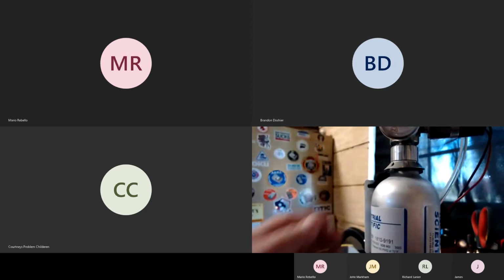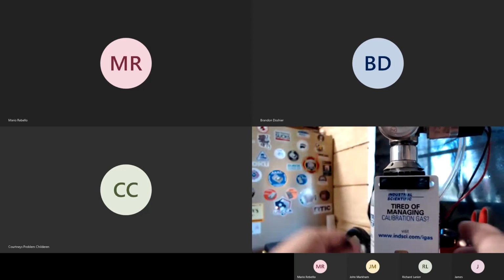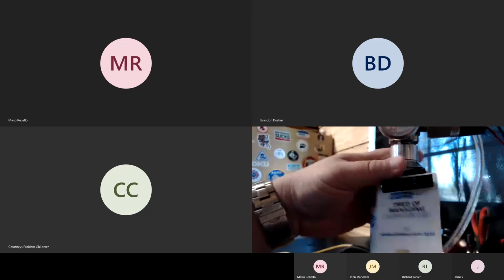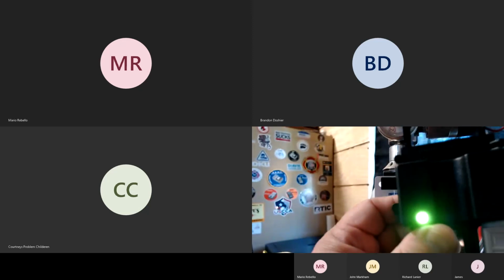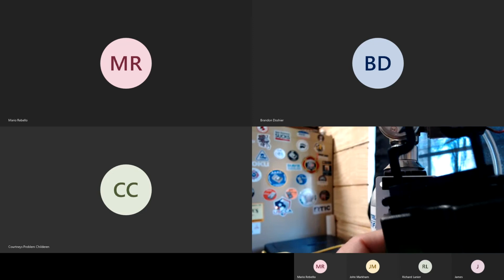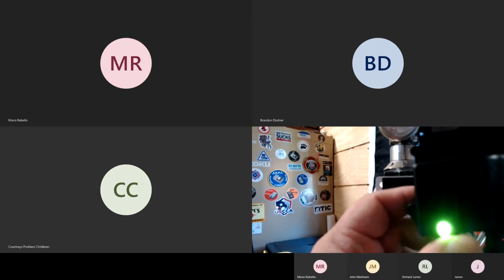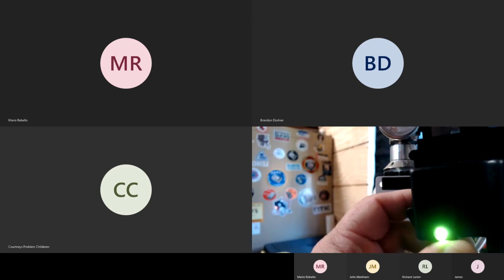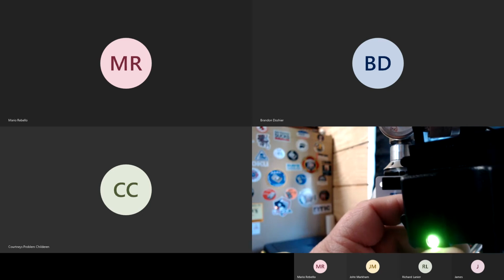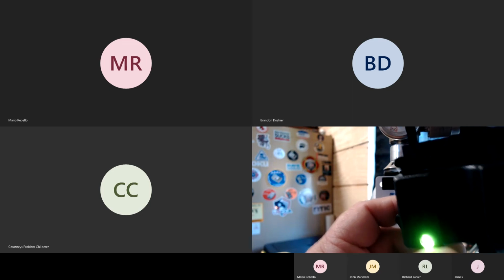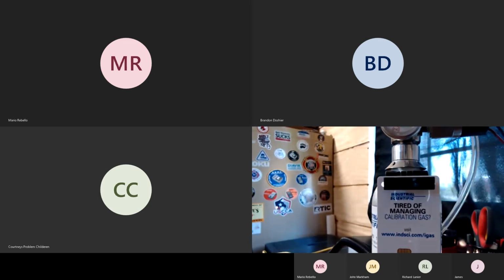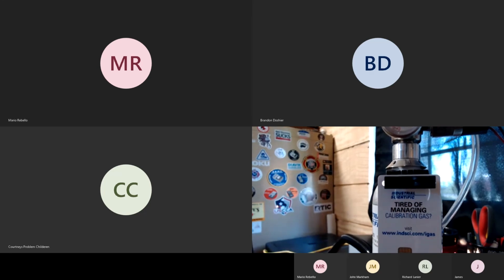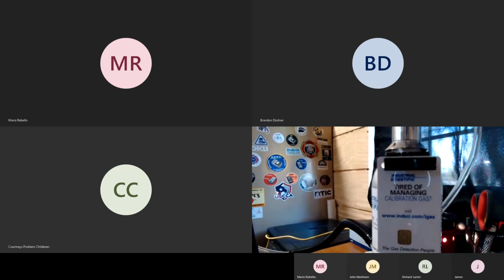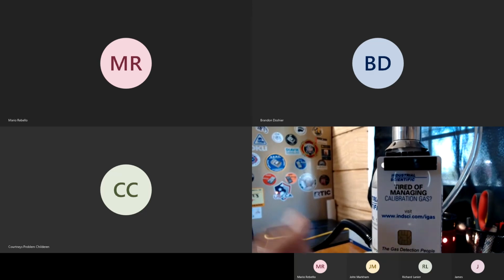Now what I have to do is connect up the card reader. One thing that you'll notice, and I pointed this out earlier, is that even without the card in there, it's got a green light. That's because the green light just indicates that there is power going to the card reader. That's it. It does not say that it's reading the card, or that it's reading the card successfully, anything like that. All it's saying is there's power to the card reader. So don't trust that little green light to tell you that everything's good.